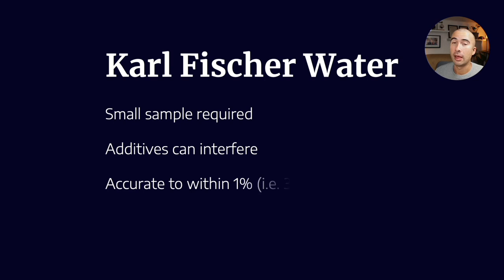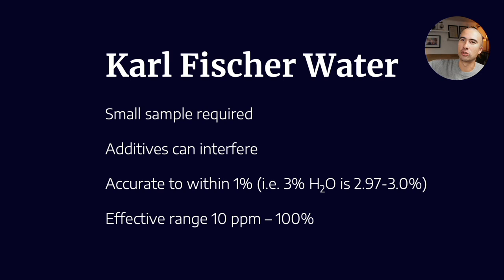But despite that, it's generally accurate to within about 1%. So as an example, if we measured 3% water, the tolerance on that we're saying is between 2.97 and 3.03%. And the effective range is about 10 parts per million right up to 100% water. So it's a very effective method for measuring very small and very large quantities of water.